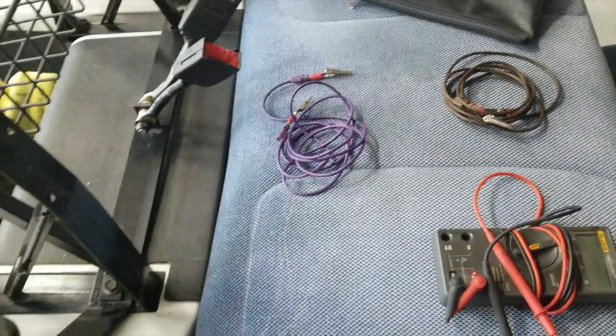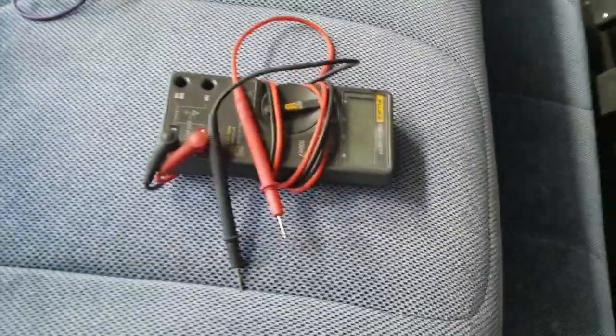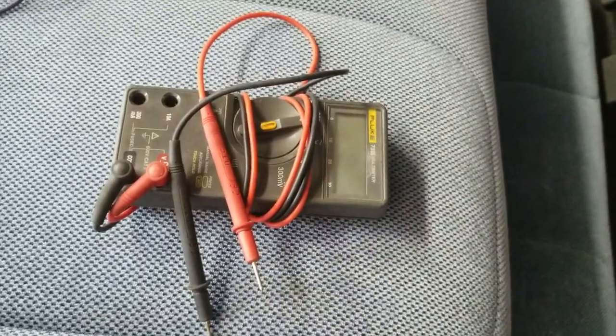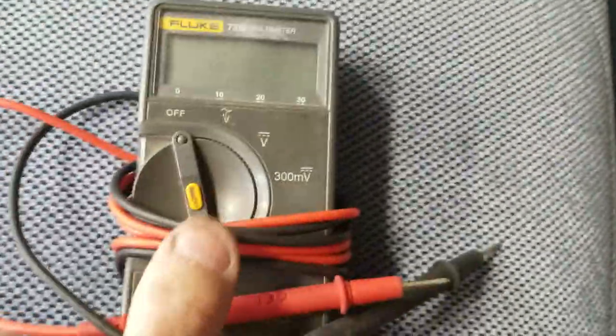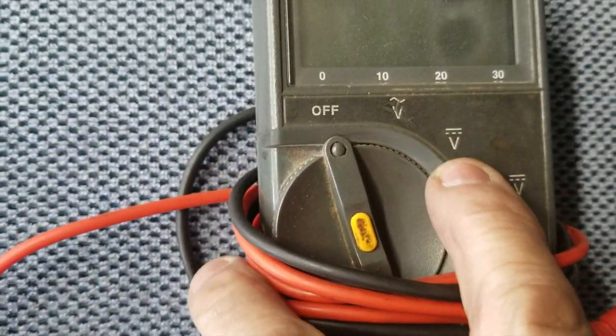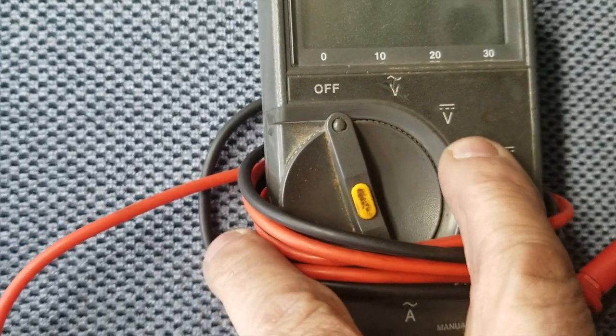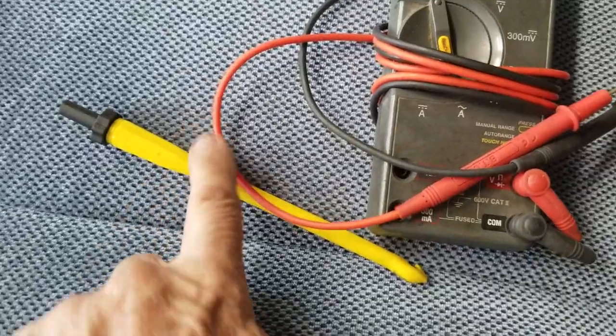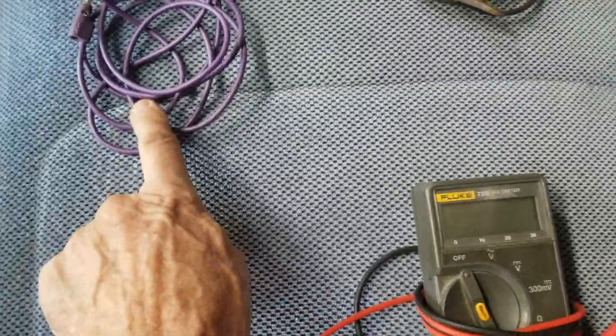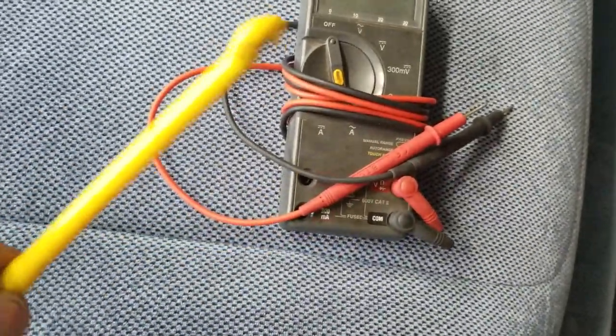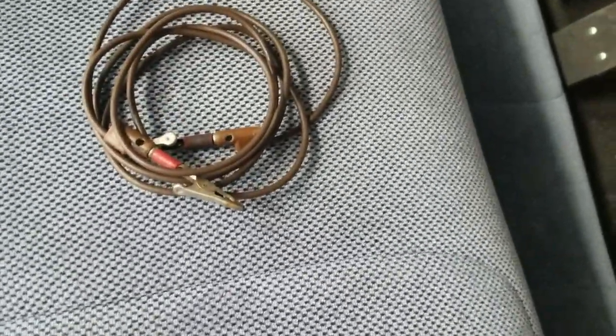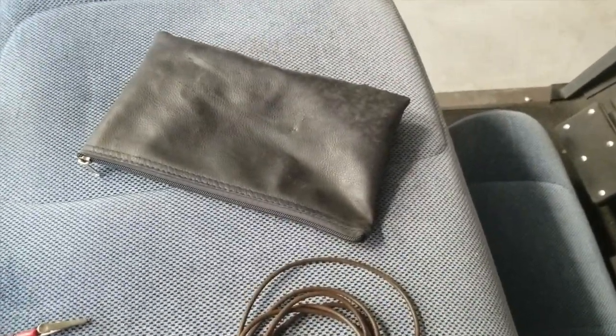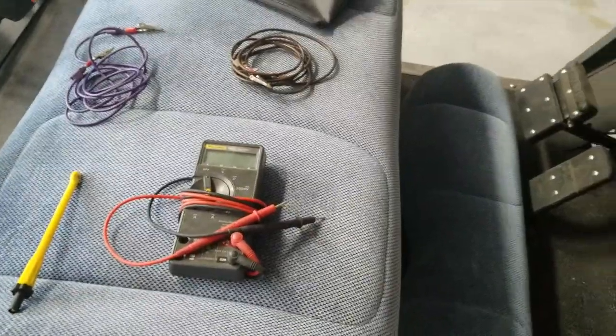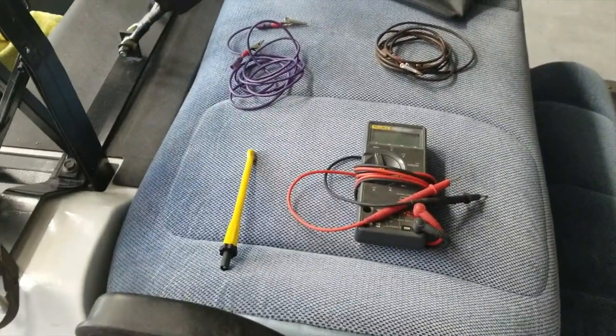And the other end of that jumper wire, let's say purple, I'm going to hook the purple wire to here, and then hook it to the red positive probe on my meter. I'll put the meter on the DC setting, which is the voltage, the V with a straight line - the wavy one is AC, this is DC, non-pulsing. So I'm going to hook this on one of those wires under there, this purple wire onto here, the other end onto the red probe. Then I'm going to take this brown wire, hook it to the negative probe on the tester, the voltage meter, and the other end of that brown wire, I'm going to go to a battery negative. That way, I should have a complete circuit to whichever wire I turn on over there.